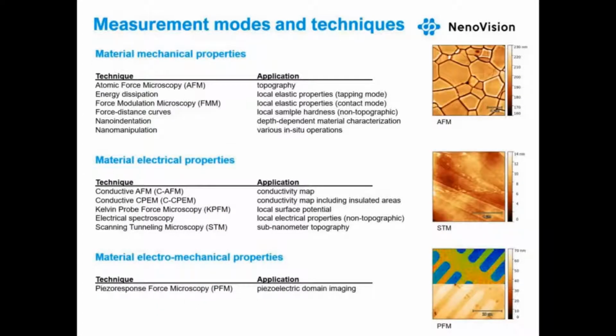LiteScope supports a wide range of measurement modes. So starting with mechanical properties, we offer topography, then measurement of local elastic properties by energy dissipation in tapping mode, or by force modulation microscopy in contact mode. You can also measure the local sample hardness by force distance curves, and then you can use the AFM probe for nano indentation and nano manipulation.